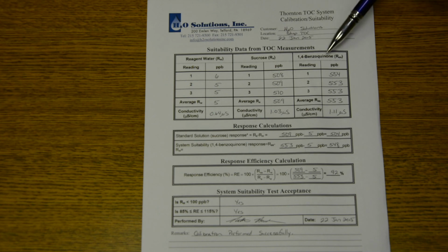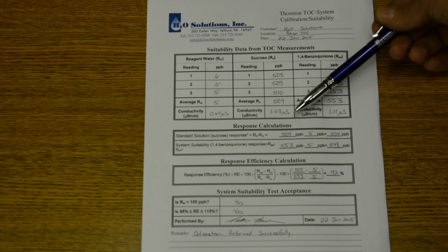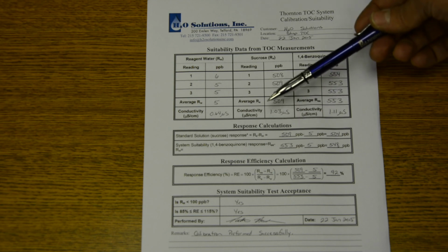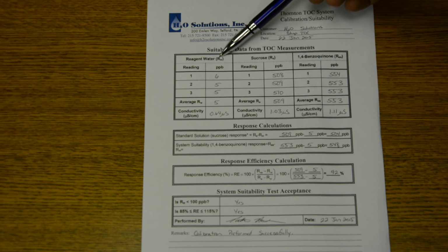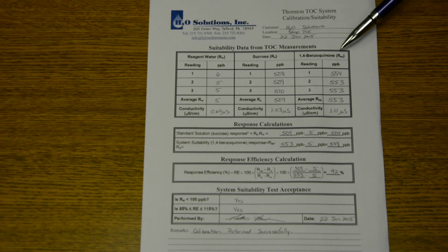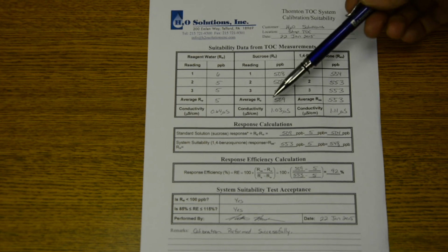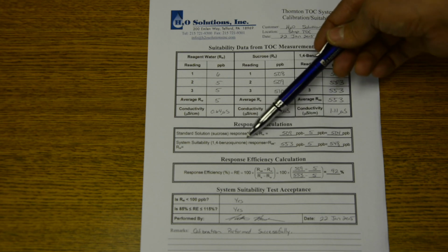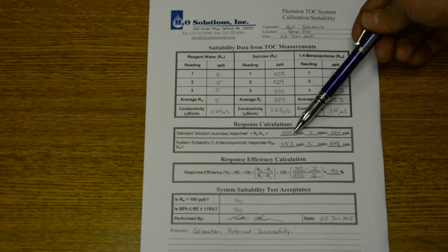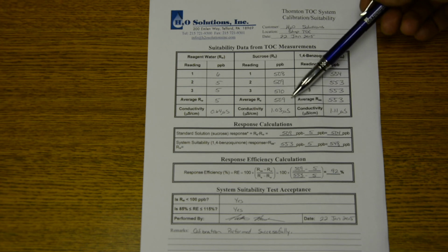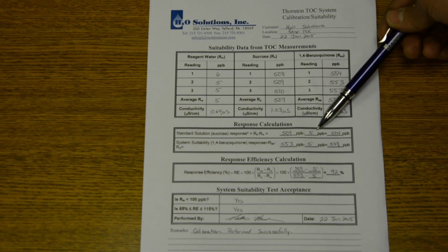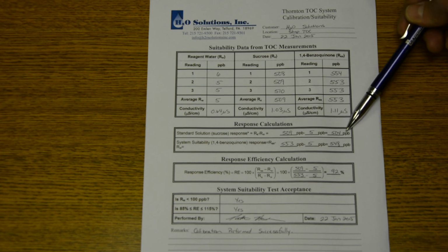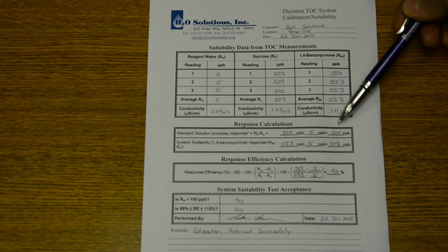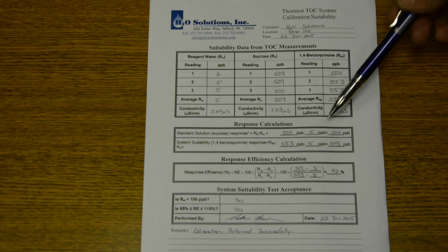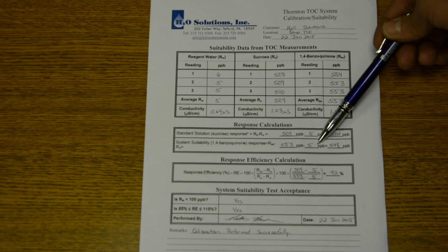Then the same thing for sucrose and benzoquinone, and then you come down here to your response calculations. At your response calculations, if you notice, they're correlated to RW for reagent water, RS for sucrose, and RSS for the benzoquinone. If you come down here, you'll see how to enter it in with your calculations. So we put 509, which comes from the sucrose, minus your reagent water, 5, and then you get 504 parts per billion. And then we come up here with the benzoquinone and take 553 and subtract 5 parts per billion out of that and get 548.